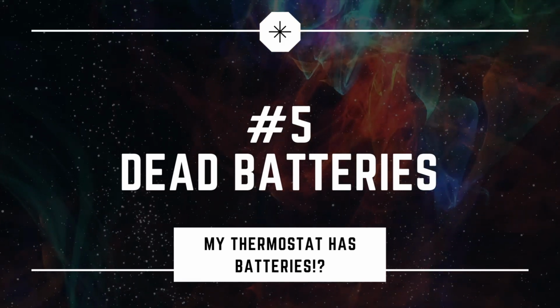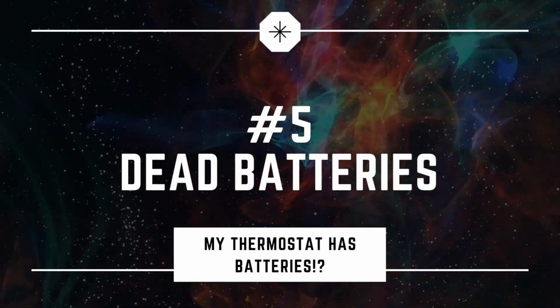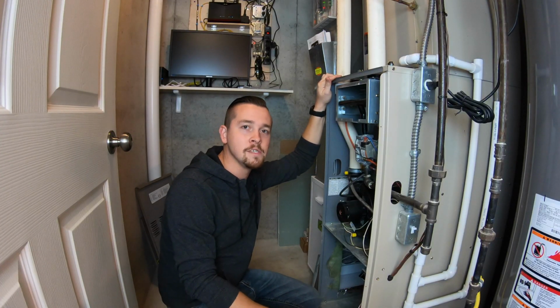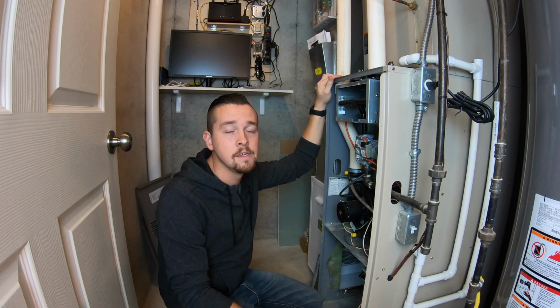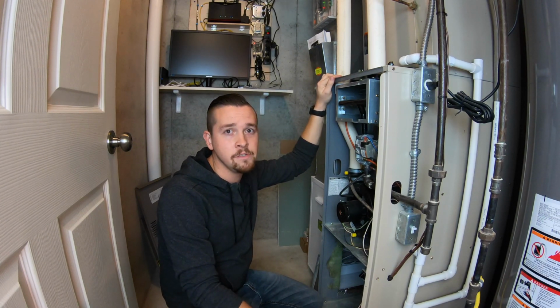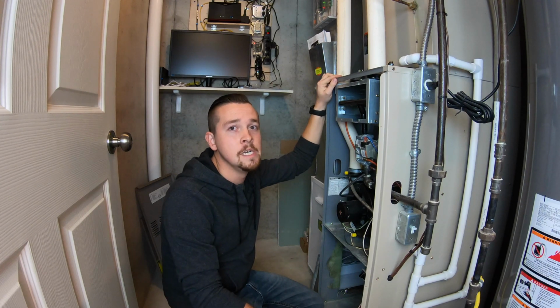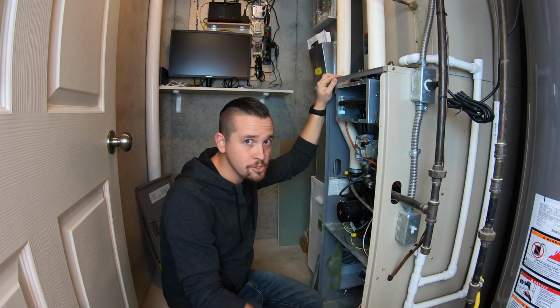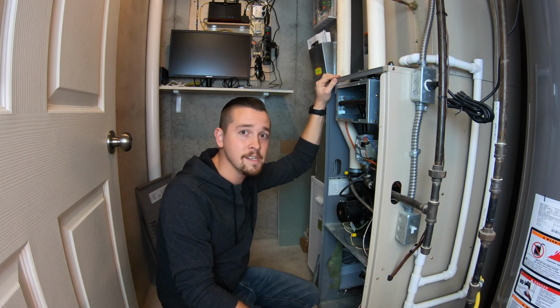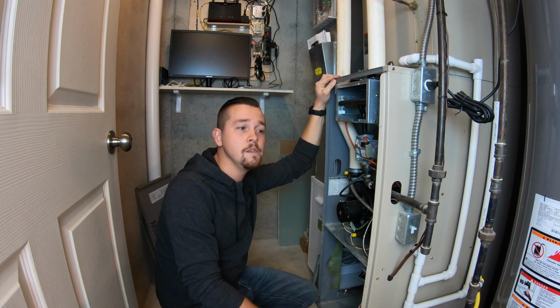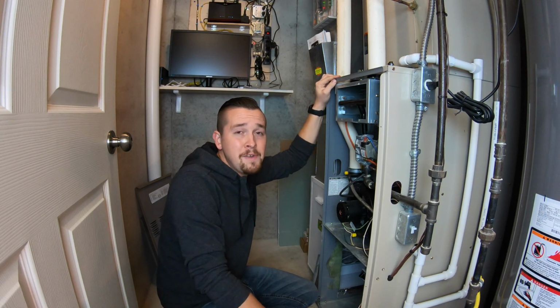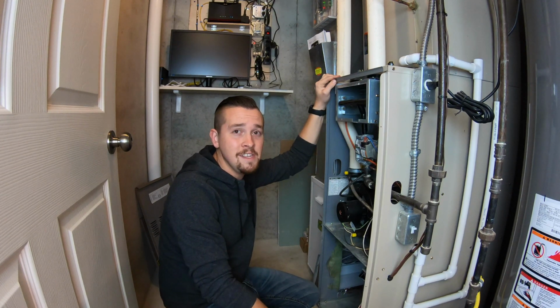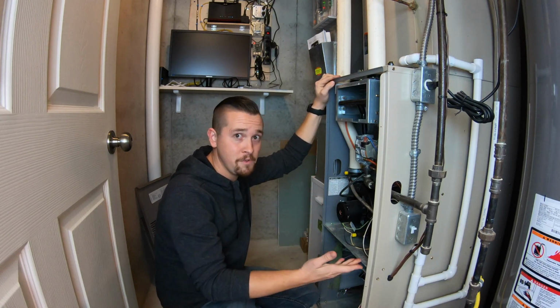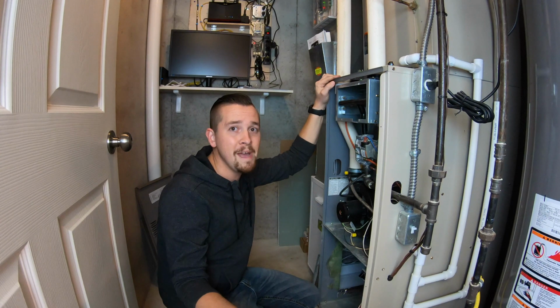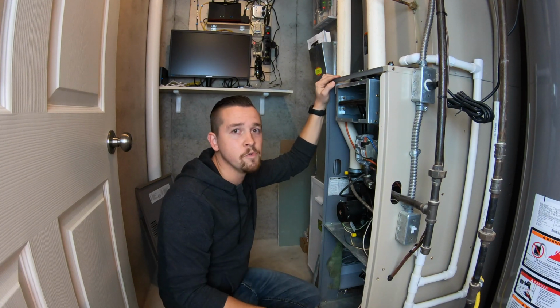Number five, dead batteries in your thermostat. Another common issue that I run across is dead batteries in the thermostat. Always check to make sure that the batteries in your thermostat are fresh and charged. A lot of times if you have a programmable digital thermostat with batteries in it, like AA's or AAA's, you'll get a low battery indicator. If you've got no display on your thermostat, then either it gets its power from the furnace and the furnace isn't giving it any power, or the batteries are dead. So always check those first before you call a technician.